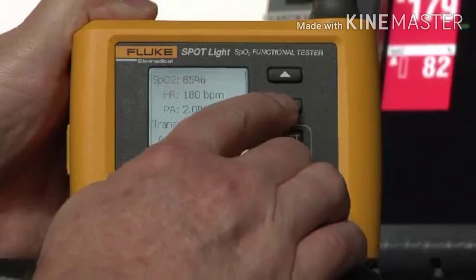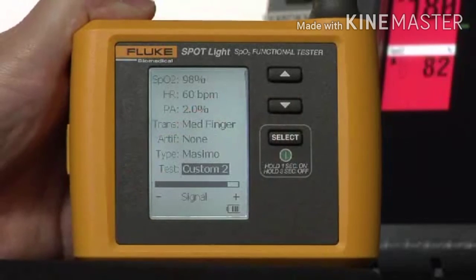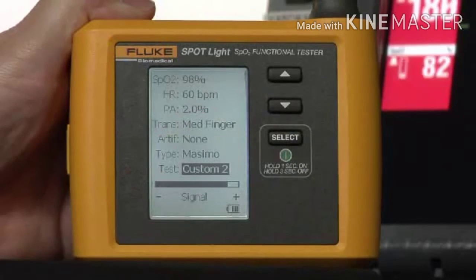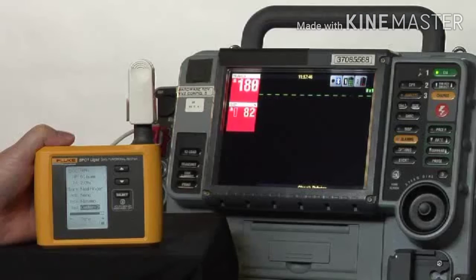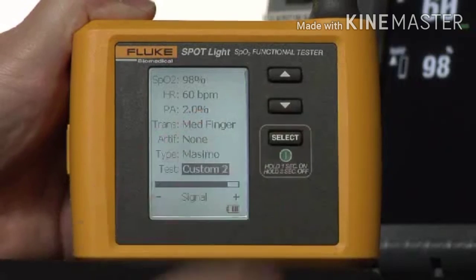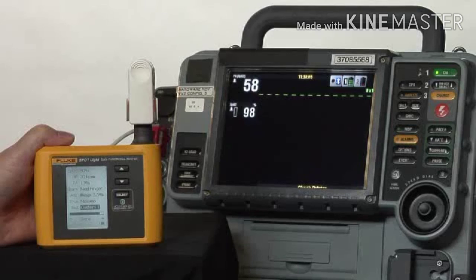And then we'll move to custom 2, which is a normal patient. We want to let the alarms continue to sound because the normal conditions will let them silence on their own, an important part of the functional test. Again, waiting for those to settle, and then we'll simply push one more time for our hypotensive patient with a low O2 saturation, low perfusion. And you'll see the alarms will sound again, this time on the low end.